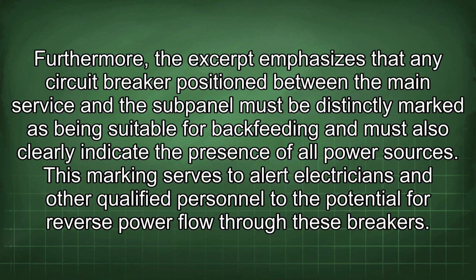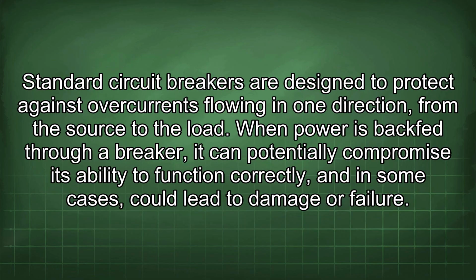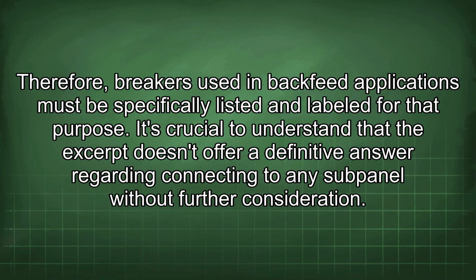Furthermore, the excerpt emphasizes that any circuit breaker positioned between the main service and the subpanel must be distinctly marked as being suitable for backfeeding and must also clearly indicate the presence of all power sources. This marking serves to alert electricians and other qualified personnel to the potential for reverse power flow through these breakers. Standard circuit breakers are designed to protect against overcurrents flowing in one direction from the source to the load. When power is backfed through a breaker, it can potentially compromise its ability to function correctly and in some cases could lead to damage or failure. Therefore, breakers used in backfeed applications must be specifically listed and labeled for that purpose.